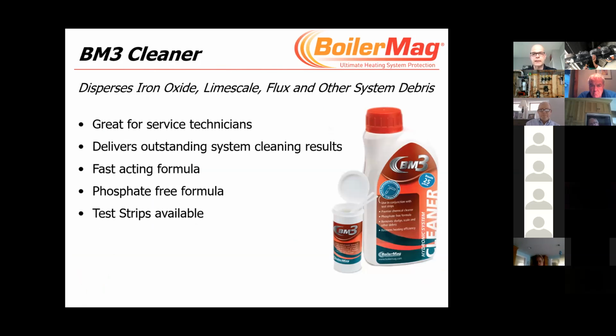The BoilerMag cleaner helps to disperse iron oxide, limescale, flux, and other debris. It's fast acting. The idea is you'd go to a system, install, add the cleaner, and recirculate it for a while - about an hour most people would do it for. Empty the system, flush it out, refill it, and then use the test strips to check you've removed most of the BoilerMag. There's a concentration chart on the back. You need to remove as much as you can from the system.